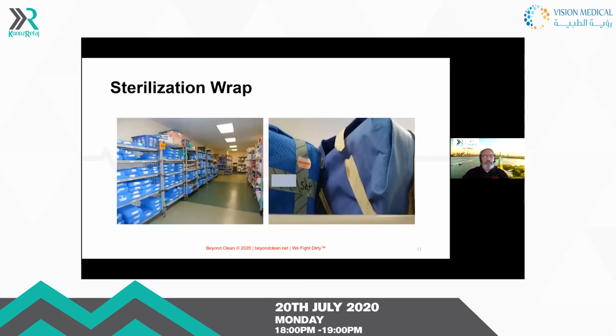And as you can see, a lot of the manufacturers now that make these blue wraps, they will tell you that they do not want you to stack them, because when we think about those 4 standards, do not crush, bend, compress, or puncture, as you stack them, they can be compressed. They can also cause punctures when you move them off the shelf or move them around. So it's really important to talk to the manufacturer again about the IFU to see if it is okay to stack these devices. And on the right, you can see the broken label. So this is a packaging you would like to pull off the shelf and re-sterilize.